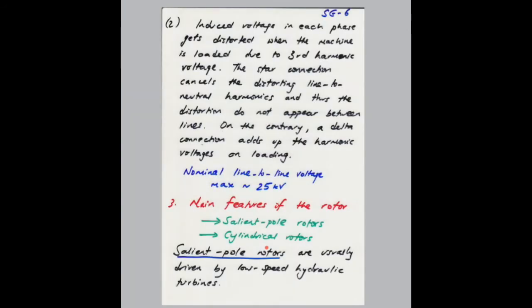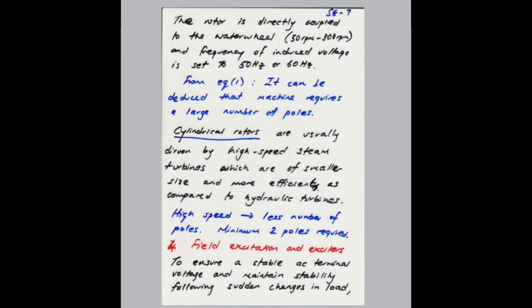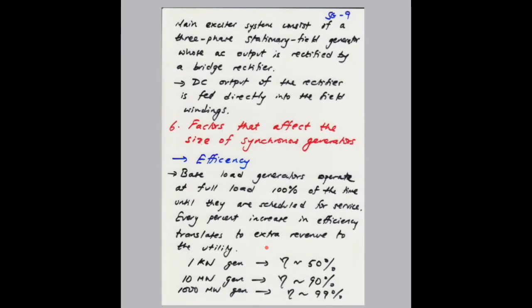So brushless excitation system is being used nowadays instead of this old technology, and obviously the main exciter now consists of a 3-phase stationary field generator whose AC output now is rectified by a bridge rectifier, and the DC output of the rectifier is fed directly to the rotor field winding.